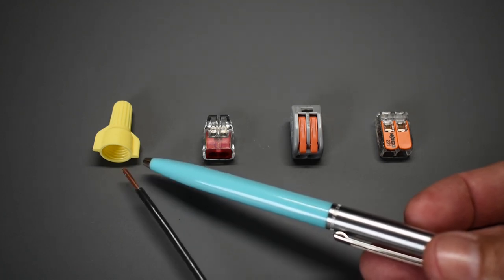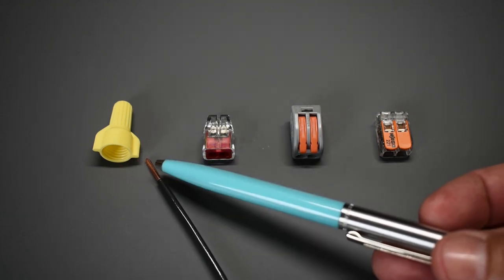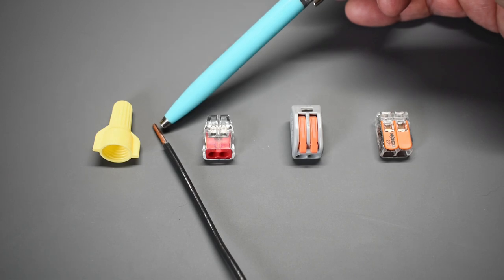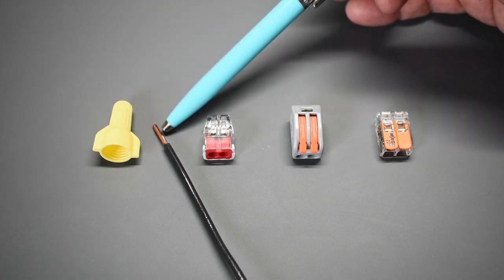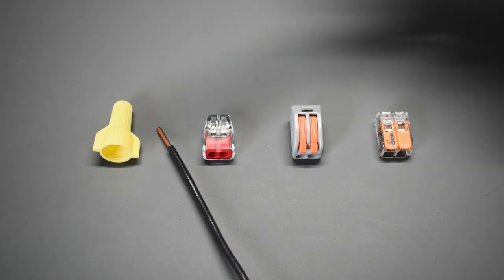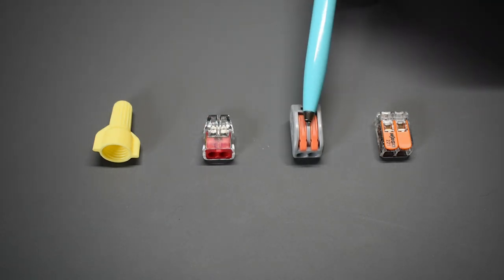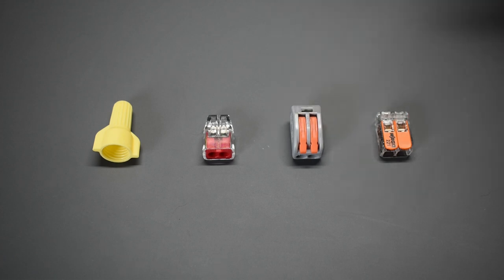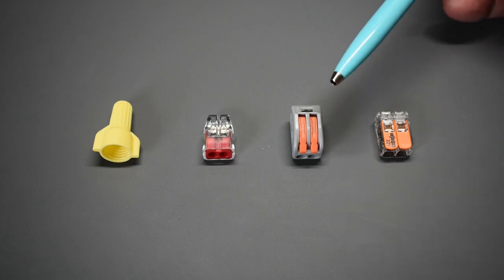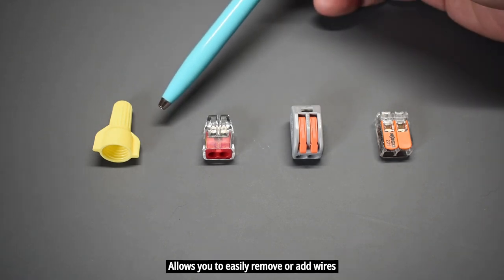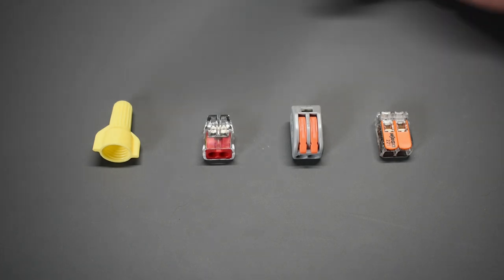If you've ever worked with wire nuts, you're going to know if you try and join four or five wires together using one of the wire nuts, it could become a little bit of a problem. One of the conductors, as it twists, may push downward, and it may not be a good connection. In that case, and the only case I would suggest, you would use one of these. This one tested better than the Wago. Look for one that has four or five levers. Slide all your conductors in, lock it down. These are ideal if you're going to be working on your wiring. But if it's new construction, definitely use these. Very few people are going to be modifying the wiring on new construction.